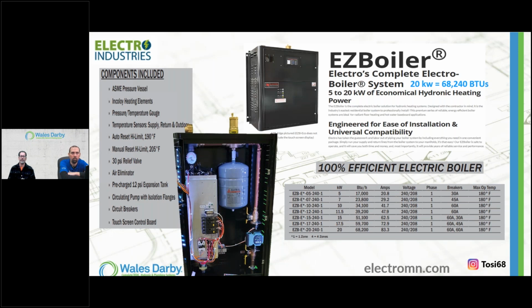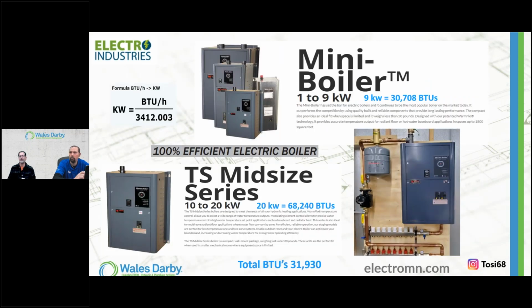So you buy it based off of kilowatts. It's packaged. It's got this primary circulator. There is no primary secondary needed. Can it be? Yes, it can. Expansion tank, all things above. We have the disconnect in here. You have some high limits. You have your elements, rather. I get a little tongue-tied with that word, but nice piece of equipment here. You can buy it single zone, 4 zone. You can buy it with a digital touchscreen controller versus maybe analog, more watered down, price point driven. Neat stuff.